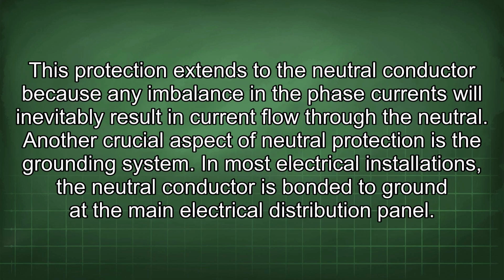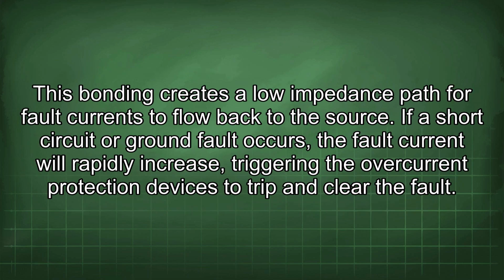This protection extends to the neutral conductor because any imbalance in the phase currents will inevitably result in current flow through the neutral. Another crucial aspect of neutral protection is the grounding system. In most electrical installations, the neutral conductor is bonded to ground at the main electrical distribution panel. This bonding creates a low impedance path for fault currents to flow back to the source. If a short circuit or ground fault occurs, the fault current will rapidly increase, triggering the overcurrent protection devices to trip and clear the fault.